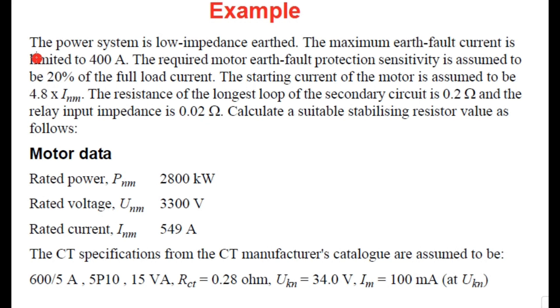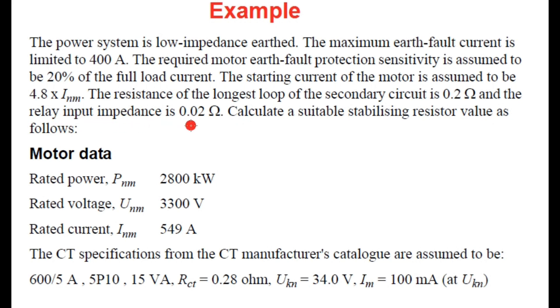The power system is low impedance earth and the maximum earth fault current is 400 A. The required motor earth fault protection sensitivity is 20% of full load current. The starting current of the motor is 4.8 times the nominal current, i.e., 4.8 × 549 A. The resistance of the longest loop of the secondary circuit is 0.2 Ω and the relay input impedance is 0.02 Ω.